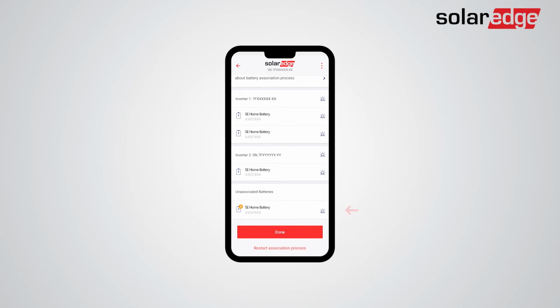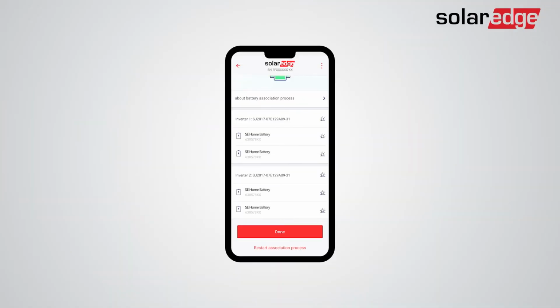Batteries that failed the association will be placed in power-saving mode until the troubleshooting is complete and won't be included in smart energy management, self-consumption, or backup operation. We recommend troubleshooting any installation issues as soon as possible. After troubleshooting, you can reset the association process by tapping Restart Association Process. Note that if you troubleshoot the battery at a later time, you will need to repeat the configuration process.